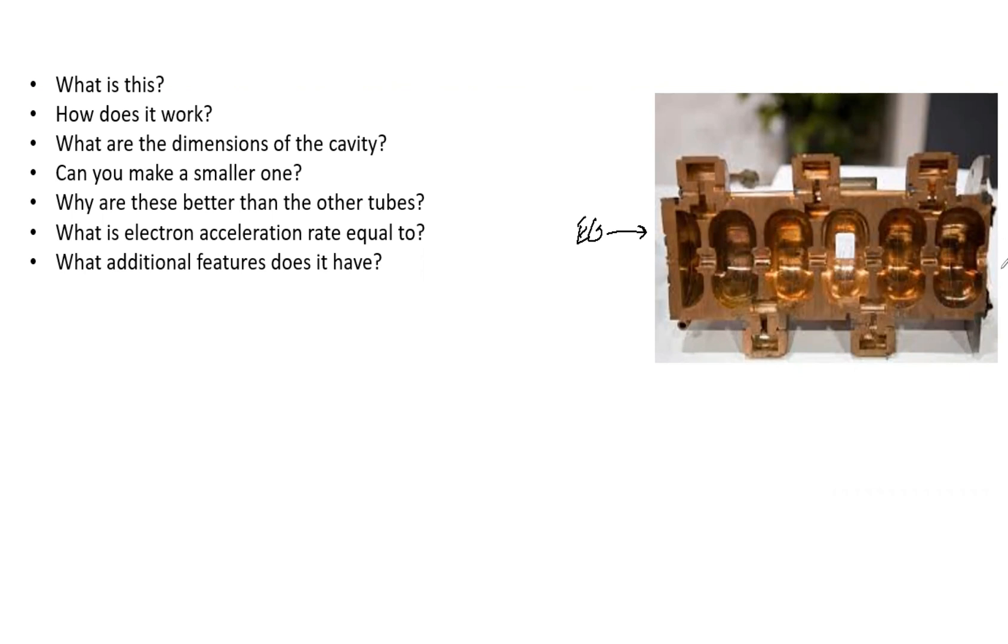When you are looking at this structure, we have standing wave, we have traveling wave, but you need to be able to analyze and pick up based on a picture or diagram which one is which. So what you want to do is look at these side cavities that will help you determine that. You see these main cavities, then you see these side cavities - that is a standing wave accelerator structure.